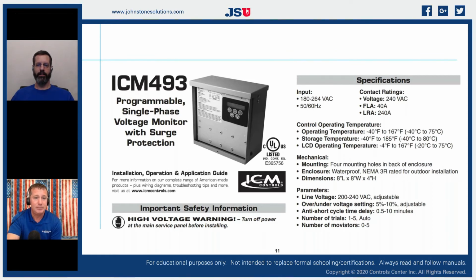I also like that most manufacturers have a 10% voltage variance. So if you have 240 volts coming in, it can have a 10% above or below allowance on the boards. But that one, you can actually dial it in. You can tune it in to a smaller amount. So I actually have mine set at a 5% tolerance, my actual ICM, so that my boards never have to go into their fail safe. Exactly, extra insurance. And that's adjustable for under and over between 5 and 10%. So a lot of flexibility and adjustability with that control. That's the reason for me, it's the best piece of equipment that I've encountered yet.